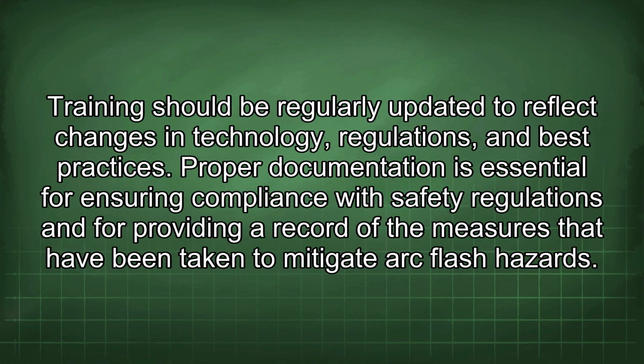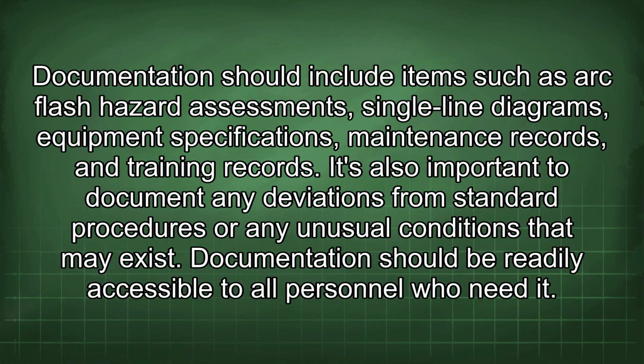Training should be regularly updated to reflect changes in technology, regulations, and best practices. Proper documentation is essential for ensuring compliance with safety regulations and for providing a record of the measures that have been taken to mitigate arc flash hazards. Documentation should include items such as arc flash hazard assessments, single-line diagrams, equipment specifications, maintenance records, and training records. It's also important to document any deviations from standard procedures or any unusual conditions that may exist. Documentation should be readily accessible to all personnel who need it.